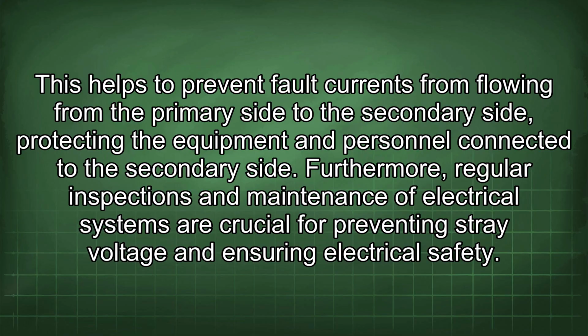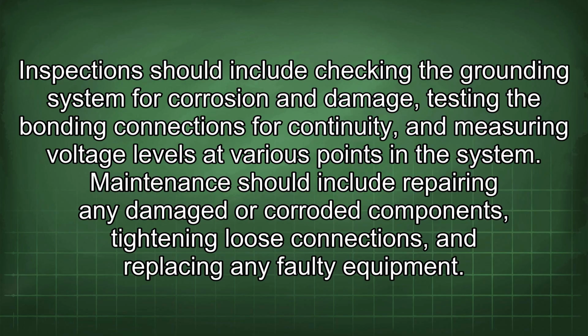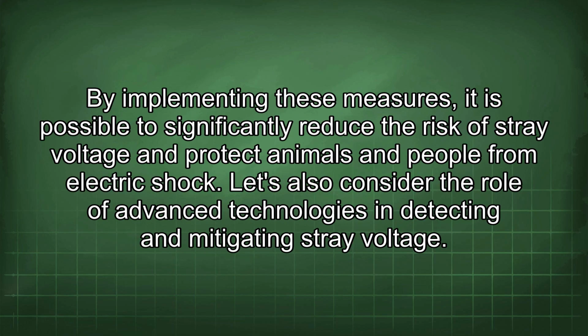Furthermore, regular inspections and maintenance of electrical systems are crucial for preventing stray voltage and ensuring electrical safety. Inspection should include checking the grounding system for corrosion and damage, testing the bonding connections for continuity, and measuring voltage levels at various points in the system. Maintenance should include repairing any damaged or corroded components, tightening loose connections, and replacing any faulty equipment.